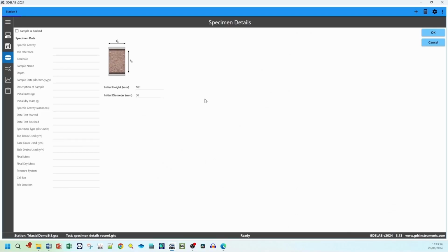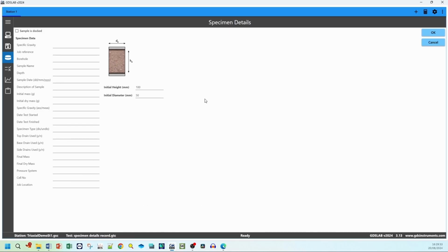Hello and welcome to the GDS Lab version 3.3.3 video tutorial, Specimen Details. The focus is on understanding how to zero axial displacement and back volume when starting a test, ensuring accurate calculations.